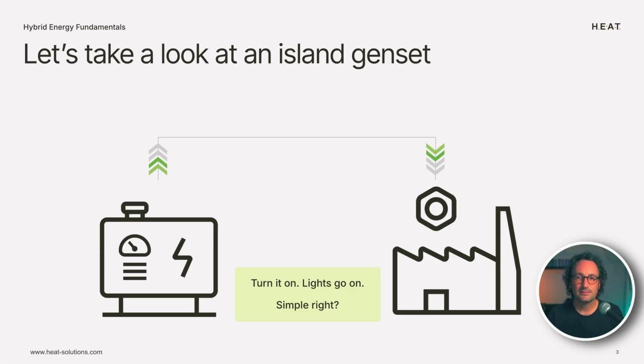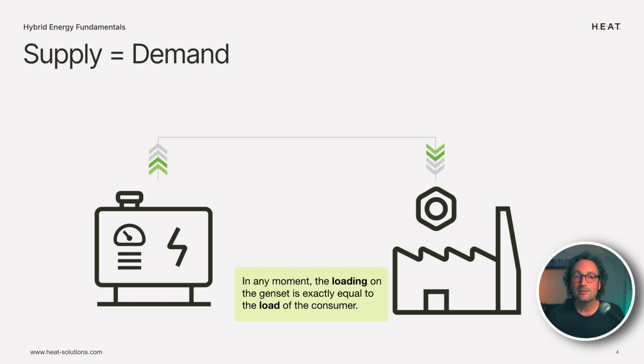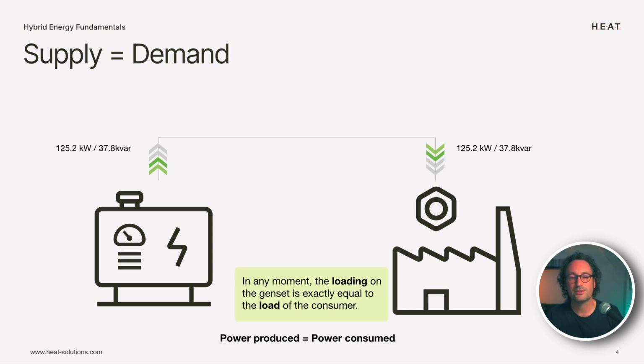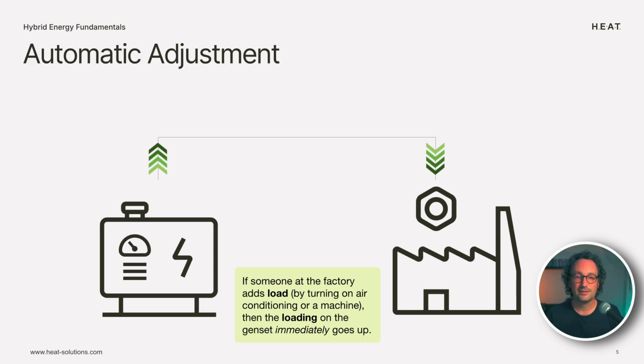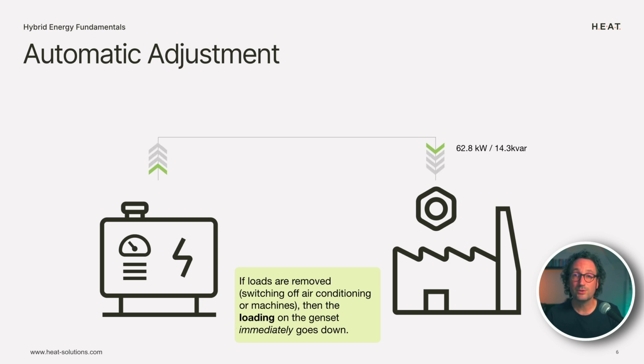If you imagine an island that has just one single diesel genset and one little factory and no public grid connection, you can probably already intuitively tell nobody needs to go and tell that genset how much power to produce. In any moment on this system, the loading on the genset is going to be exactly equal to the load of the consumer. So if the consumer is consuming 125.2 kilowatts, our diesel genset is producing 125.2 kilowatts. So the power being produced is always equal to the power being consumed. And there's an automatic adjustment here. If someone adds load at the factory and the power goes up, then the power will go up on the diesel genset as well. And it's automatic in the other direction. If someone reduces loads at the factory, then the loading on the genset immediately goes down to match it.